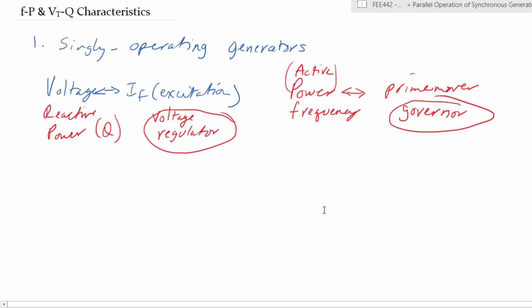So getting back to this, when a generator is operating, those are the two key elements that you will need to take care of, or remember. Always remember, the voltage regulator varies voltage and reactive power. The governor varies active power and frequency. Okay, so having known that, let's now get into how generators operate as the loads are varied, because this is all about the characteristics of generators when they are working under load.